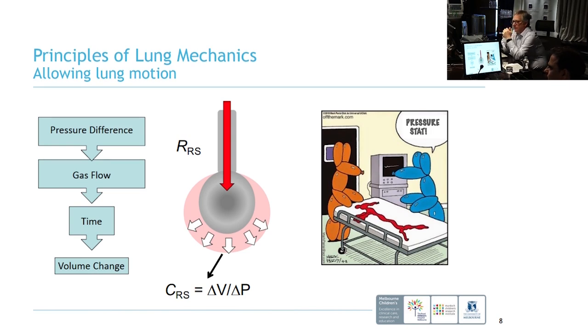The inverse of that, of course, is compliance. Compliance is delta V over delta P, or tidal volume divided by delta P on a conventional ventilator. A poorly compliant lung needs a lot of pressure for a small amount of volume change. So we need to overcome those two forces. We don't need to give any more pressure than is required, but it's very hard to understand that without fancy measurements, which we don't have.